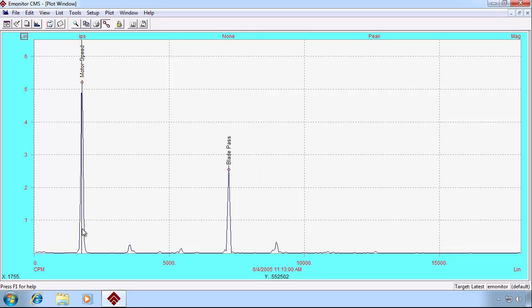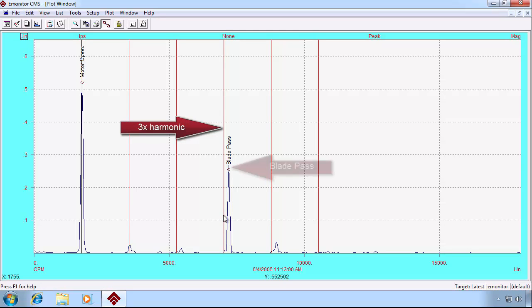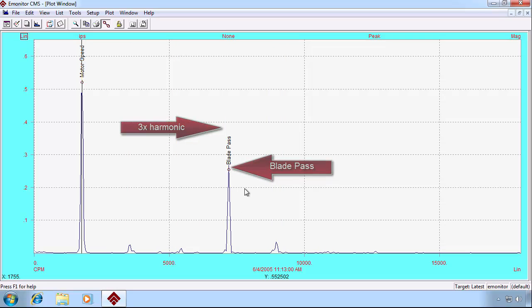So if we click back on our motor speed and then hit the H key to turn on our harmonic cursor, we notice that the cursor for the 3x harmonic is not the same as the blade pass. There are different frequencies.